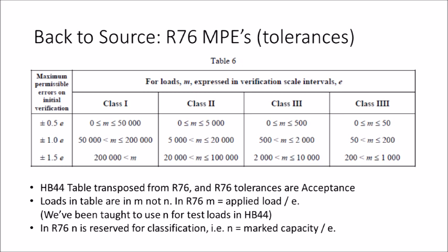Now, if we go back to the source, the R76 table of MPEs, maximum permissible errors, a couple of things I want to do for orientation purposes is first notice that this table is transposed from the table in Handbook 44.